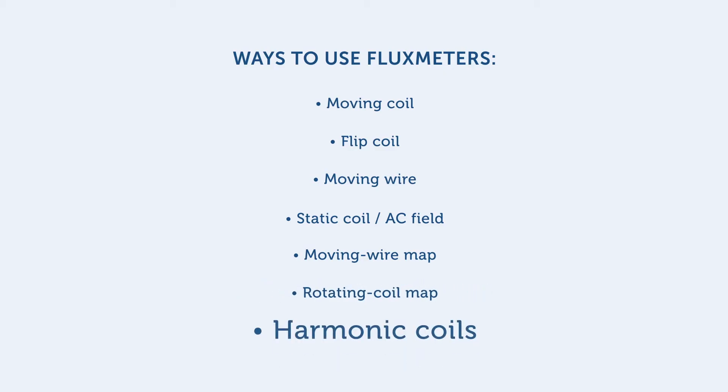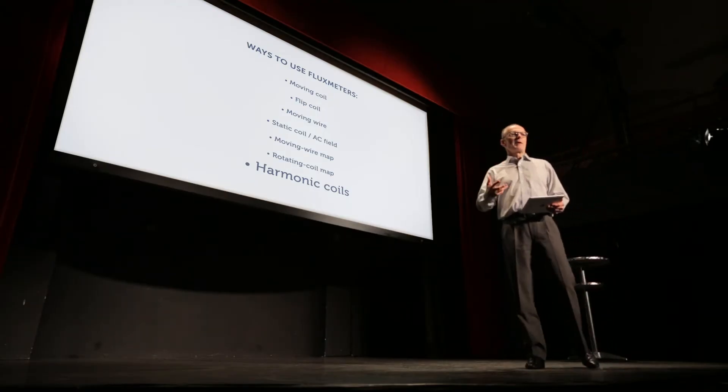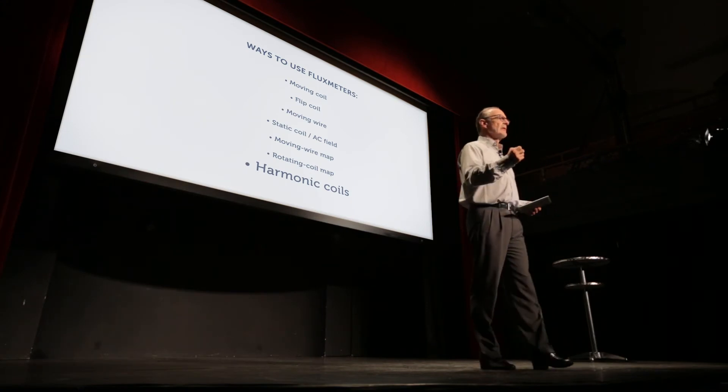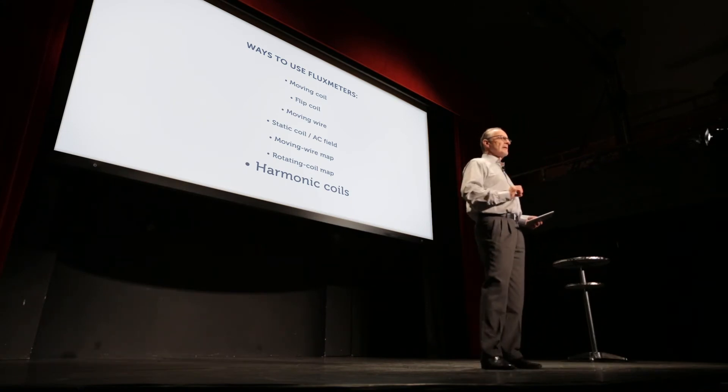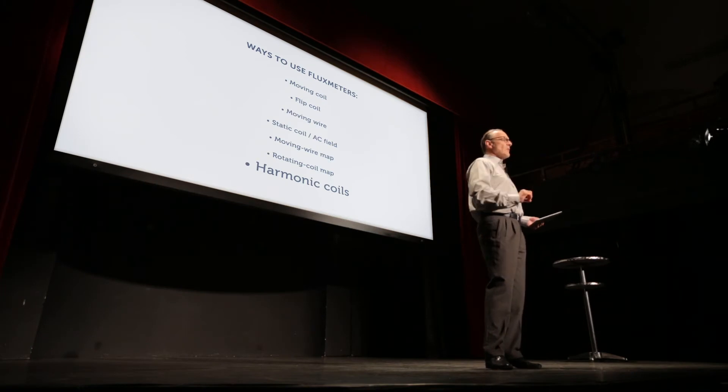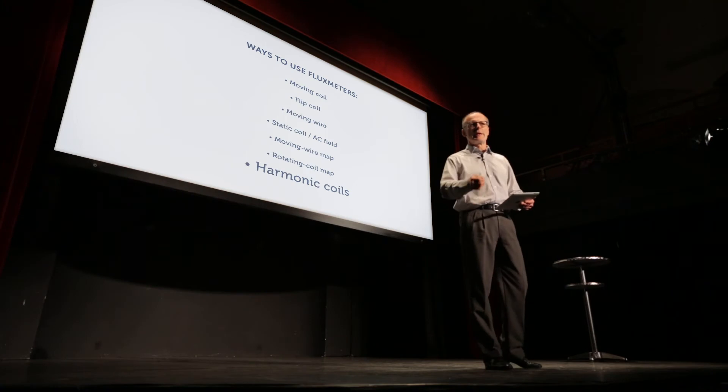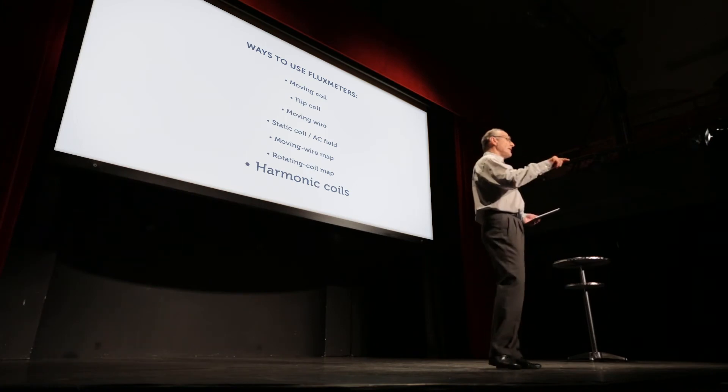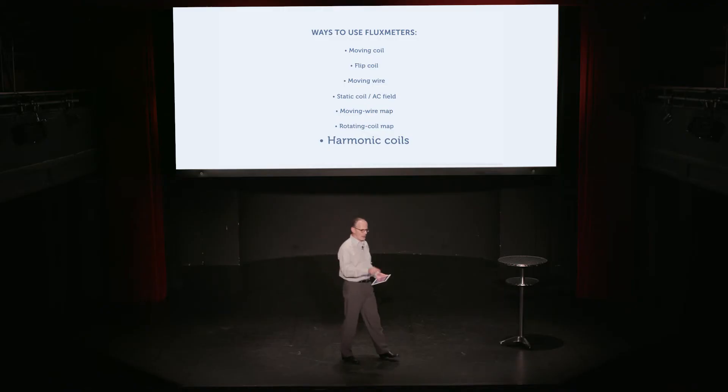One extension of the rotating coil measurement is the concept of bucking coils. Now, the idea here is that, let's say we're measuring a dipole magnet, but we know what the dipole field is that we can measure with an NMR magnetometer.